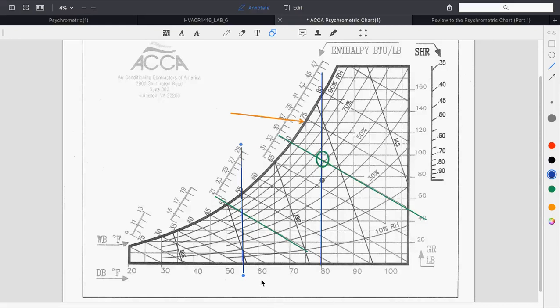What have we done? We've cooled the air, but the air coming off the coil actually has a higher relative humidity percent. That sounds counterproductive, but that's not the humidity in the room — that's just the humidity as part of the cooling process. When this air goes into the room and mixes with the rest of the space, the wet bulb is still down, so there's less moisture in the air.